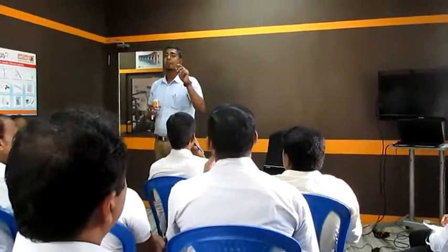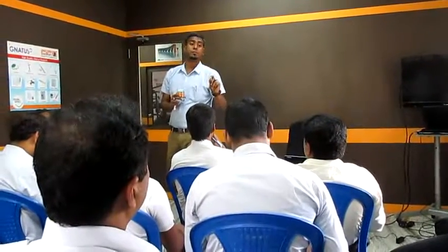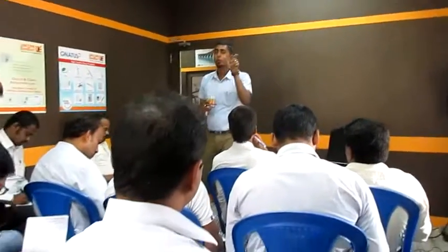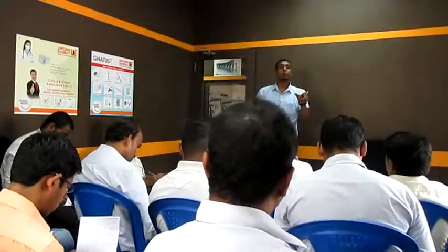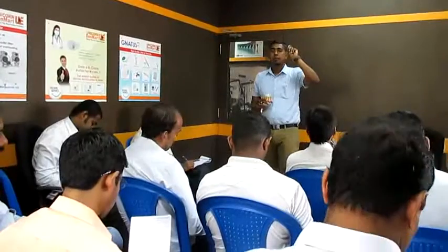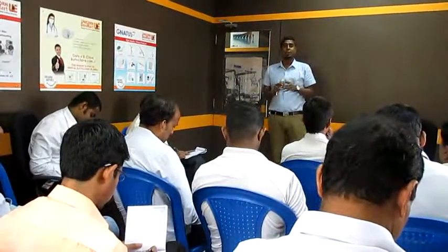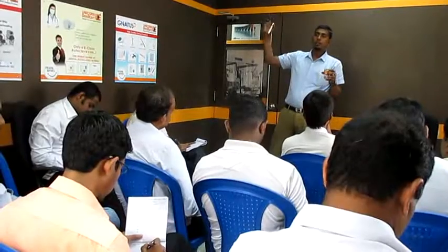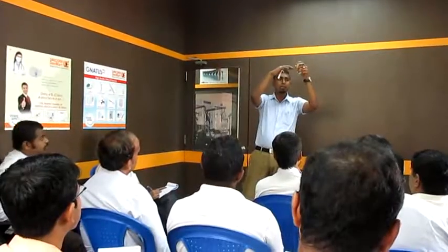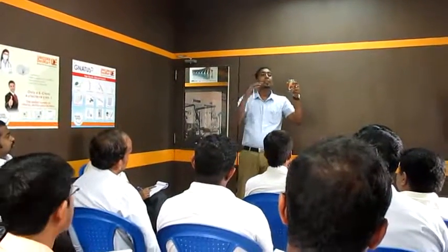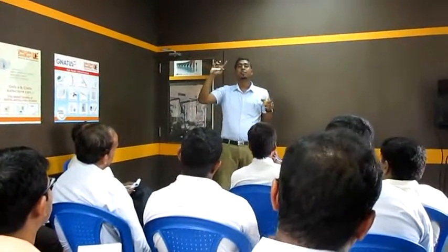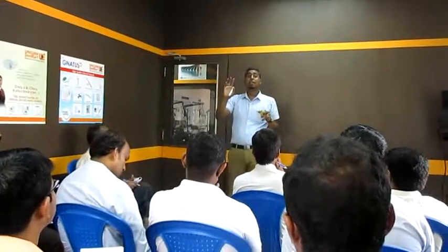The focal spot is a part of your X-ray tube. Unless you are able to see the X-ray tube, you will not be able to see the focal spot. Okay, now the question is, what is the focal spot? Another name of the focal spot is target. This is the point where the electron comes from the cathode, from the filament, and hits. It will hit on the target or focal spot, and from that point the X-ray will generate. It will not come out, it will generate.